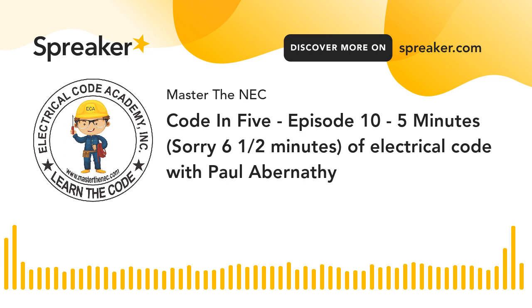Now, under the equipment provisions, here's what it says. The determination of terminal provisions of equipment shall be based on 110.14(C)(1)(a) or (C)(1)(b). We're going to do (C)(1)(a) today. It says, unless the equipment is listed and marked otherwise, and that is an important statement because usually it is, conductor ampacities used in determining equipment termination provisions shall be based on Table 310.16, which is our ampacity table, as appropriately modified by 310.12, which is the 83% rule for conductor sizing for feeders and services. Not what we're talking about today.